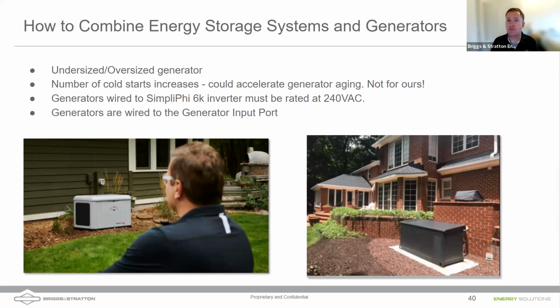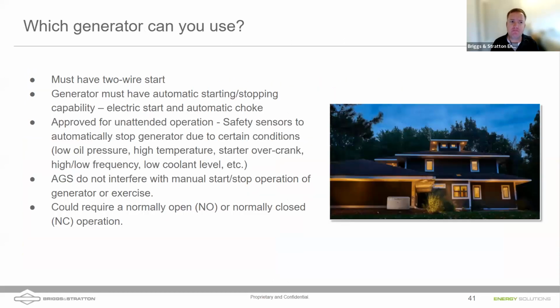You do have to feed 240 volt generator power into our inverter. And I think that is also the case on a lot of Solarcs. Maybe that Sol-Ark 5K can take in a 120 volt generator as well. And you have to wire it into the gen port. The generator must have 2-wire start signal capability, with automatic starting and stopping. This isn't like a portable generator with a push button start, right? These are standby generators that have the ability to start up.